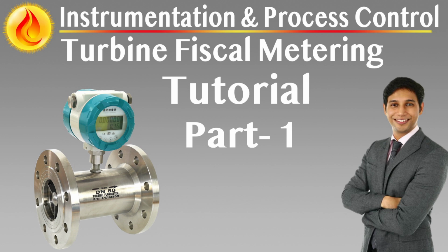Calibration interface for master verification. Prover piping must include standardized connections for recalibration against a portable master prover or traceable reference meter. These provisions support periodic verification campaigns and regulatory audits, ensuring long-term credibility of the prover volume and derived meter factors. Calibration procedures must be documented and align with national standards.